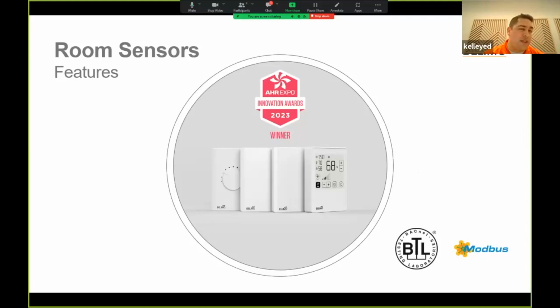We also have temperature compensation. We have an onboard temperature sensor, and we measure the internal self heat of the sensor and dynamically adjust the output temperature to the BMS. So it's a truer temperature reading, versus having to read the temperature inside the device, which is not really important for our applications. The third big thing, in my eyes, for why we won this innovation award is dynamic pressure compensation. We know CO2 is a gas. Depending on altitude and elevation, density changes. It has an effect on response time and accuracy for CO2. We have an onboard pressure sensor within the device itself. In real time, we're measuring the pressure and offsetting our CO2 values to remain as accurate as possible. You could take one of these off the wall in Miami, install it in Denver, Colorado, and you still have tried and true accurate CO2 readings.